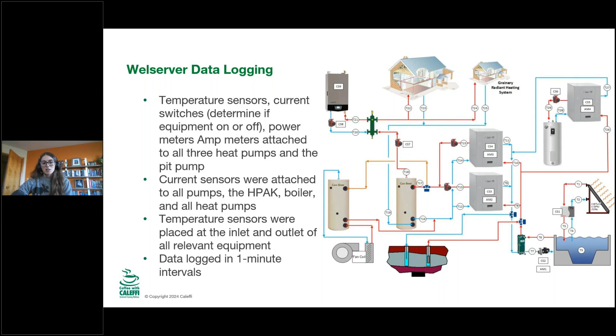I did have a lot of issues, unfortunately, with data quality. So we put some power meters on each of the heat pumps, and for heat pump 1 and heat pump 2, we had to basically disregard that data because you can see that there was some sort of electrical interference there. The heat pumps were never shown as turning off, which I knew they did at periods of time. And so unfortunately, we weren't able to use some of that power meter data for heat pump 1 and heat pump 2, but we were able to use it for heat pump 3, which was the domestic hot water heat pump. And then, only about half of the sensors logged data.